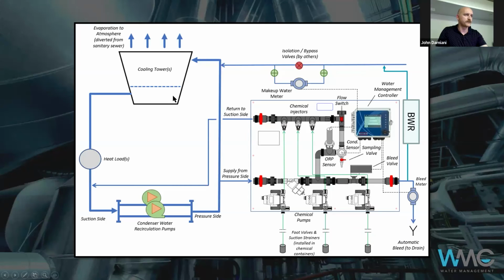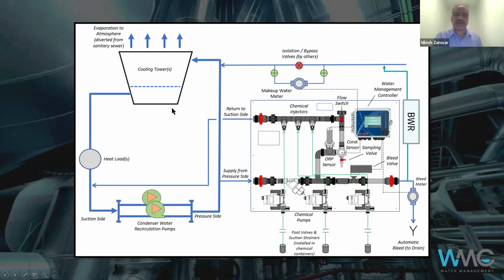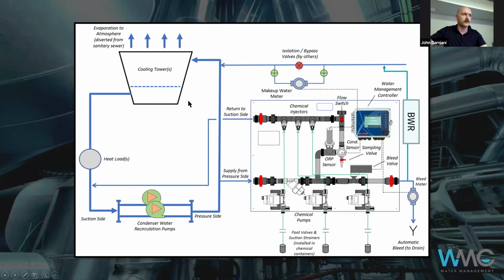But in countries where the temperatures are normally about 20-25 degrees Celsius average, yes, we end up using water continuously. So most of the time you're going to use water when you need cooling. It just means you can get what's called free cooling if you drain it and just run it with air, turn the fans on. But if you have water in here, you're going to have a spray pump that's just going to circulate water up to your top deck to your nozzles, and then spray that over your tube bundle, as opposed to passing it through fill, allowing it to evaporate. So you will get evaporation from this water, but it's a contained system where your condenser water only exists really on the fluid cooler itself.